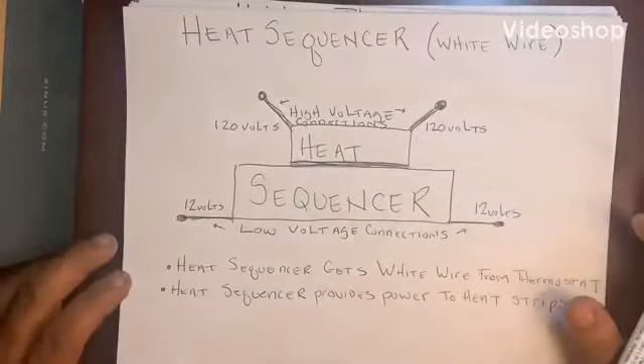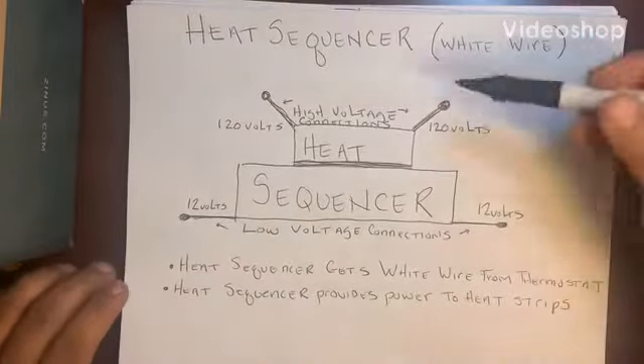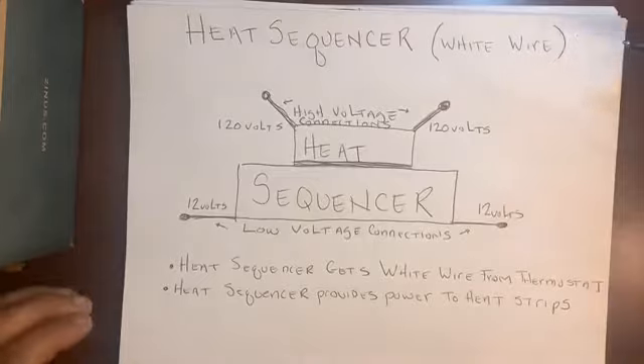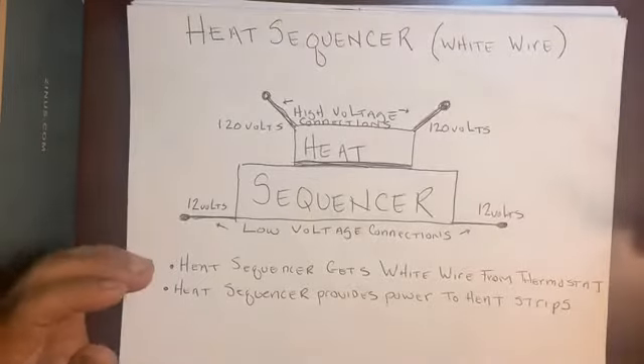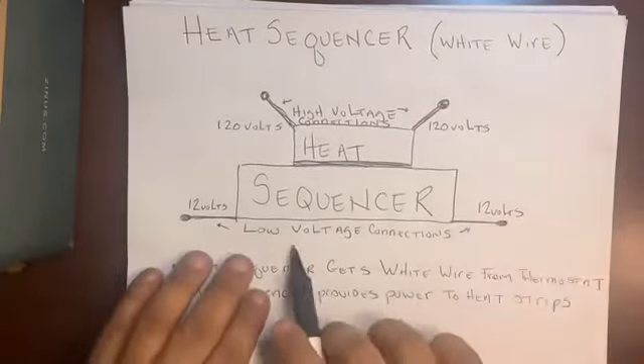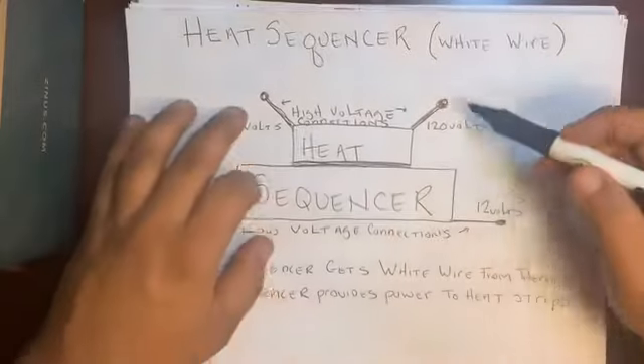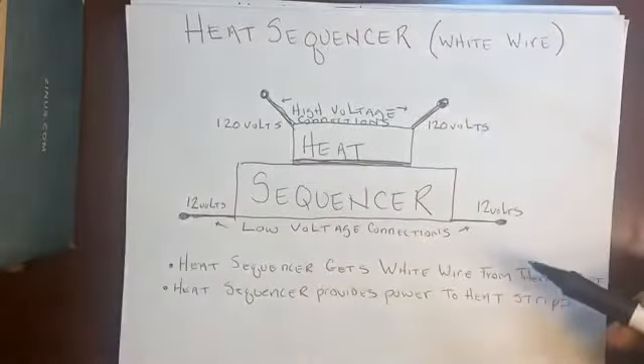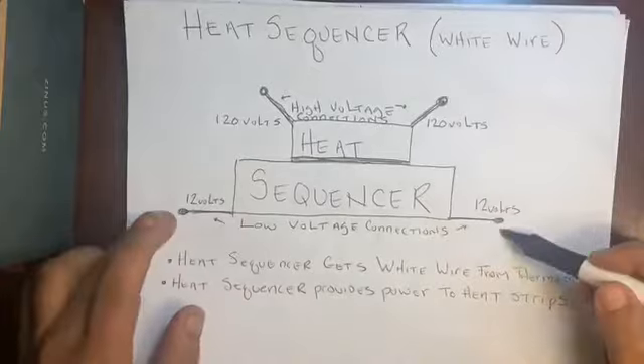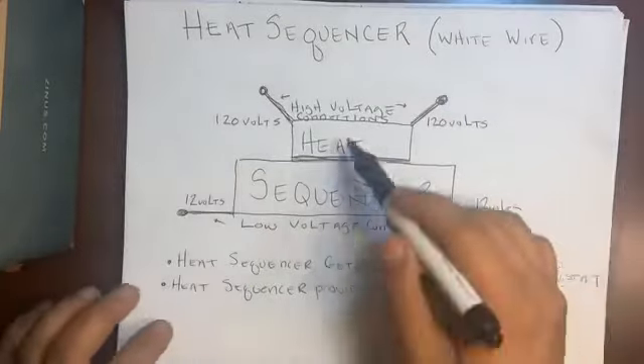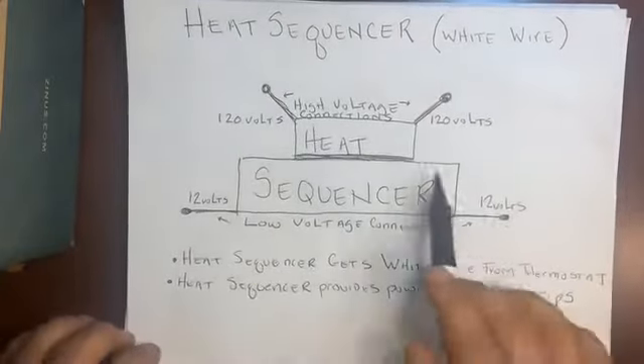We're talking about relays. We'll start with our heat sequencer relay, gets our white wire. What we have to understand about a relay is a relay has a space for low voltage connections as well as high voltage connections. So every relay will have a space for low voltage and high voltage. This is our heat sequencer. This is what it looks like on the diagram.